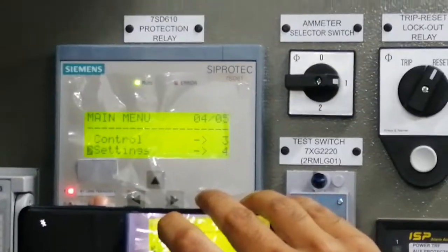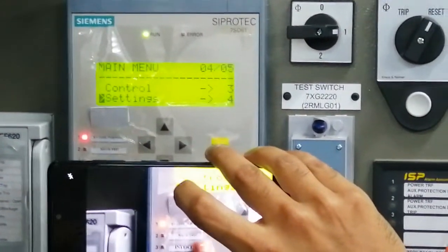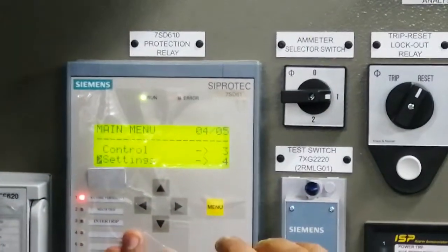As you can see now, this is the 132 kV SIPROTEC relay, and we are getting the CB close permissive. We have prepared these labels only for testing purposes, because actually this 11 kV SIPROTEC relay is installed in incomer 2 of the 11 kV switchgear, but only for testing purposes we have configured it as a 132 kV SIPROTEC relay and also prepared these labels for this testing.